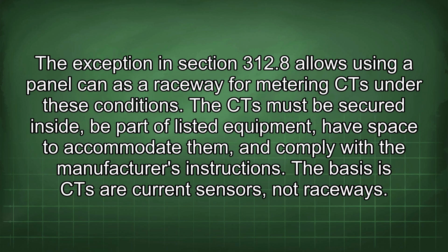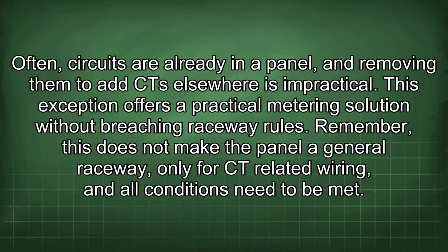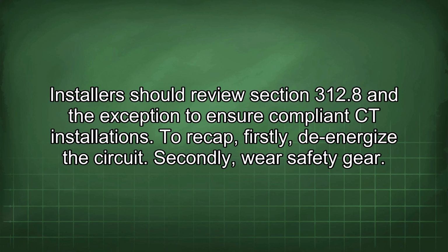The exception in Section 312.8 allows using a panel can as a raceway for metering CT under these conditions. The CT must be secured inside, be part of listed equipment, have space to accommodate them, and comply with the manufacturer's instructions. The basis of CT are current sensors, not raceways. Often, circuits are already in a panel, and removing them to add CT elsewhere is impractical. This exception offers a practical metering solution without breaching raceway rules. Remember, this does not make the panel a general raceway, only for CT-related wiring, and all conditions need to be met. Installers should review Section 312.8 and the exception to ensure compliant CT installations.